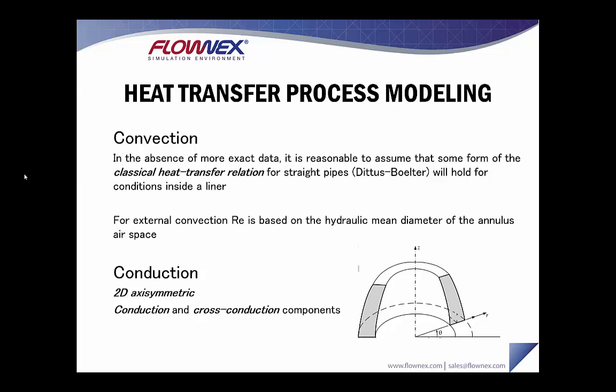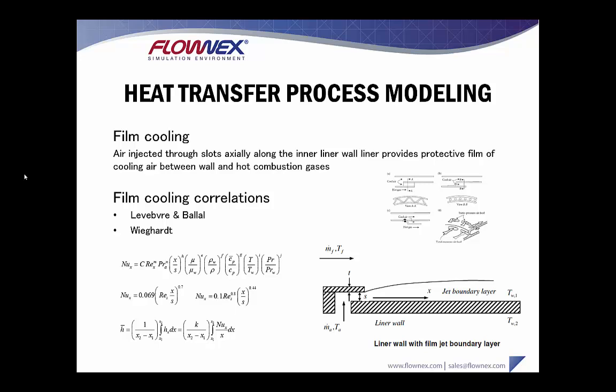With regards to convection, it's typically reasonable to assume that some form of the classical heat transfer relation for straight pipes will hold for conditions inside a liner. For external convection, the Reynolds number is based on the hydraulic mean diameter of the annular air space. Flownex also allows you to create a 2D axisymmetric representation of your conduction surfaces and model conduction and cross-conduction through those surfaces.